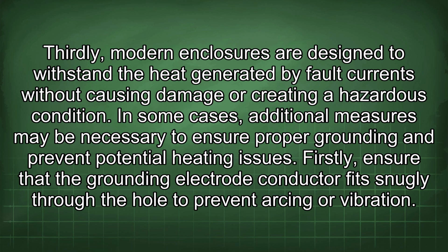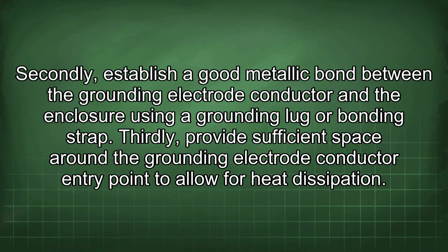In some cases, additional measures may be necessary to ensure proper grounding and prevent potential heating issues. Firstly, ensure that the grounding electrode conductor fits snugly through the hole to prevent arcing or vibration. Secondly, establish a good metallic bond between the grounding electrode conductor and the enclosure using a grounding lug or bonding strap. Thirdly, provide sufficient space around the grounding electrode conductor entry point to allow for heat dissipation.